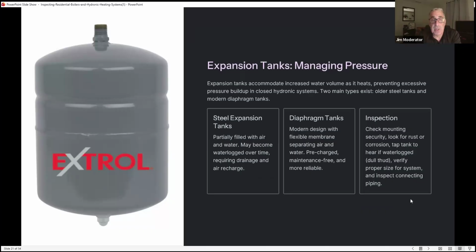Expansion tanks, managing pressure. Expansion tanks accommodate increased water volume as it heats. Water expands and contracts, preventing excessive pressure buildup in closed hydronic systems. Two main types exist: older steel tanks and modern diaphragm tanks. Steel expansion tanks, partially filled with air and water, may become waterlogged over time, requiring drainage and air recharge. Diaphragm tanks, modern design with flexible membranes separating the air and water, pre-charged, maintenance-free, and more reliable. Inspection: check mounting security, look for rust and corrosion, tap the tank to hear if it's waterlogged, the dull thud, verify proper size for system, and inspect connecting piping.